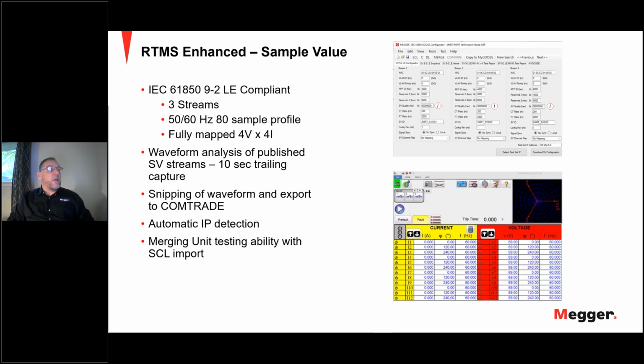Sampled values, and the Megger sampled values is in compliance with 61850-9-2 LE, where we can provide 3 streams at 50 or 60 Hertz, 80 sample profile, and we fully map 4 voltages and 4 currents. Waveform analysis of published SV streams at 10 seconds trailing capture. Merging unit testing ability is possible with SCL import.